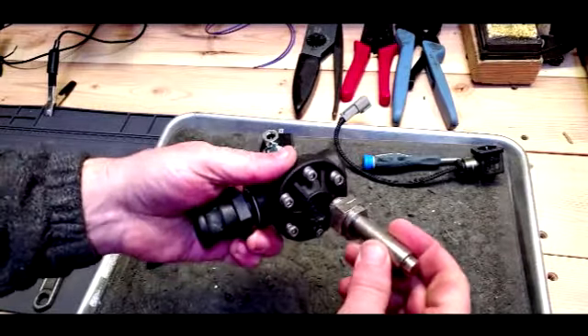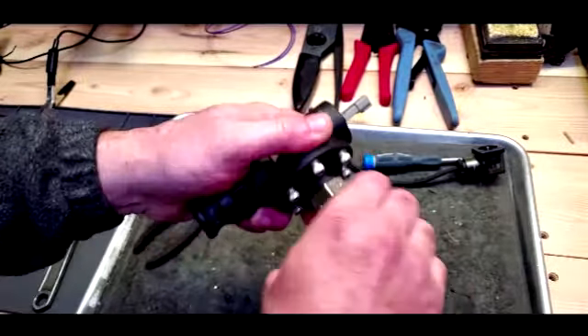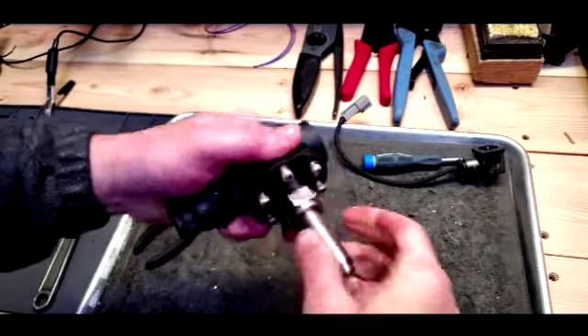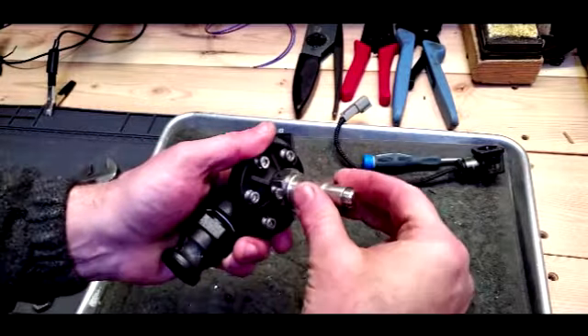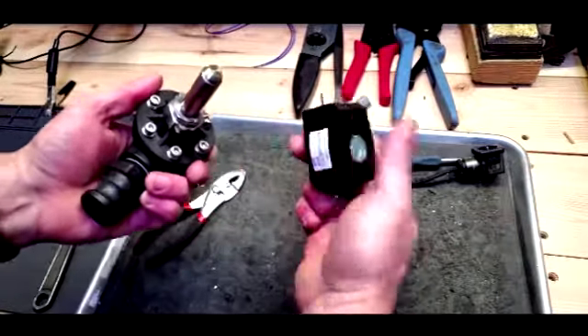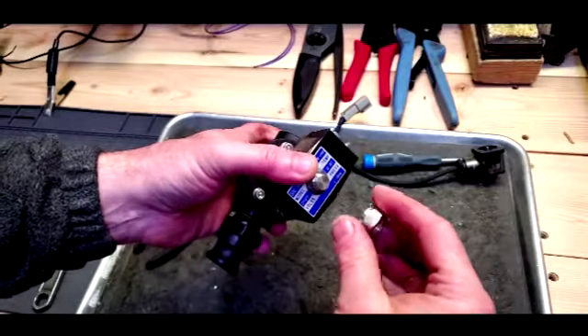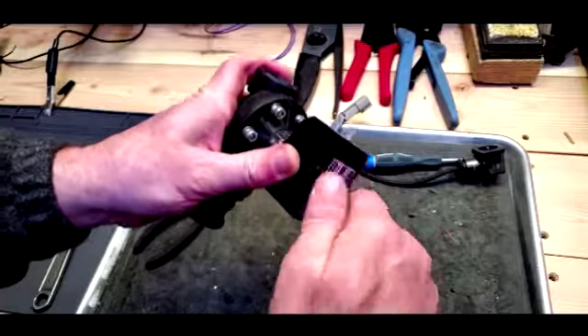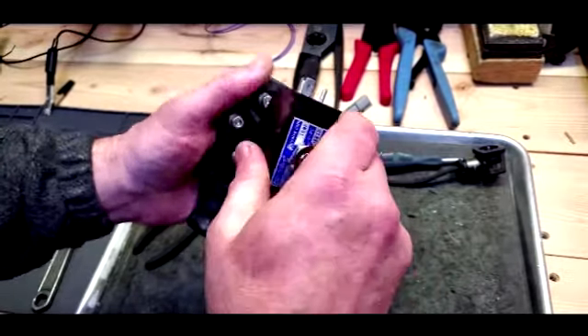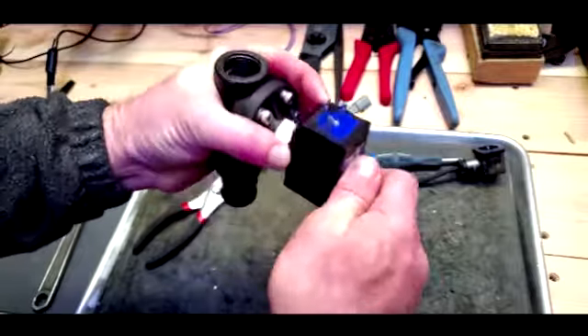Then get it tightened up a little bit, and you can reinsert it now. Again, plastic with stainless steel, so be very careful. Just take it right down until that o-ring seats, and then you can put the rest of it back together. Don't forget the washer to keep contact with the solenoid. You'll have to kind of push down on the solenoid a little bit and push on the crown nut. Then we're going to reinstall the wiring connector, and you'll be ready to go again.